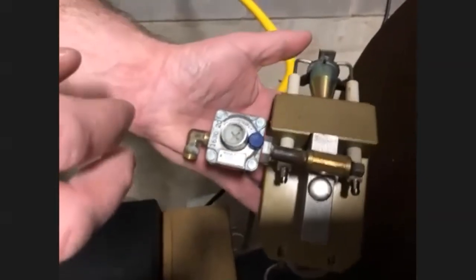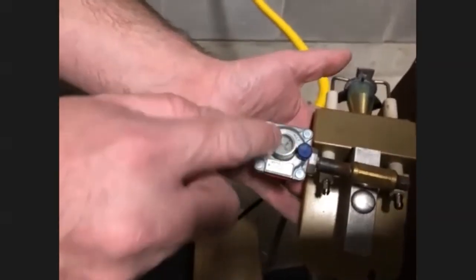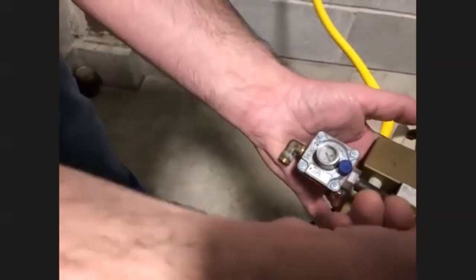When it gets to the secondary or the pilot regulator, you want to verify that there's 3.5 inches coming out of this. You can remove this plug right here and connect your manometer to it. And again, you must have 3.5 inches of water column coming out. And here we go back to that setup. We have that adjuster on this regulator, the secondary pilot regulator. To adjust this, you can remove the cap that's on there and you can adjust this accordingly. And again, you can verify all that right here.